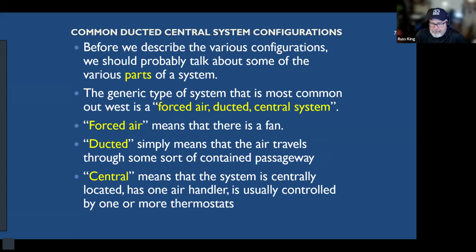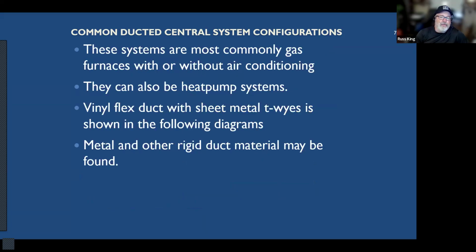Okay. Before we start talking about the different configurations, we need to talk about the terminology. So when we say a forced air ducted central system, we mean there's a fan blowing air, okay? It's ducted, so it's blowing air to the rooms, and the heating and cooling system is in a central location. All right. So pretty basic, pretty straightforward. These systems are mostly gas furnaces, but slowly switching over to heat pumps. Okay. They can be with or without air conditioning. Heat pumps have air conditioning automatically. And then the type of ductwork themselves can be sheet metal, but most common out here in California is flex duct, vinyl flex duct.